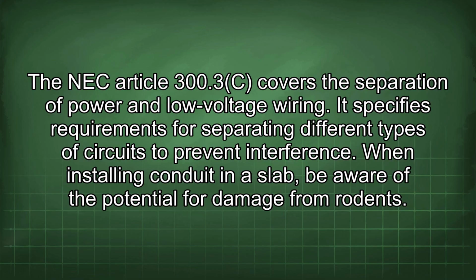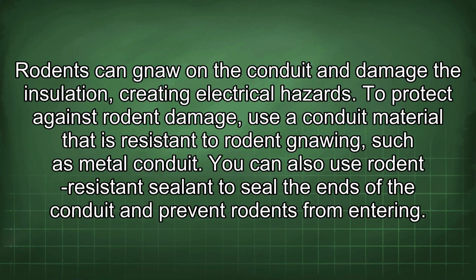When installing conduit in a slab, be aware of the potential for damage from rodents. Rodents can gnaw on the conduit and damage the insulation, creating electrical hazards. To protect against rodent damage, use a conduit material that is resistant to rodent gnawing, such as metal conduit. You can also use rodent-resistant sealant to seal the ends of the conduit and prevent rodents from entering.